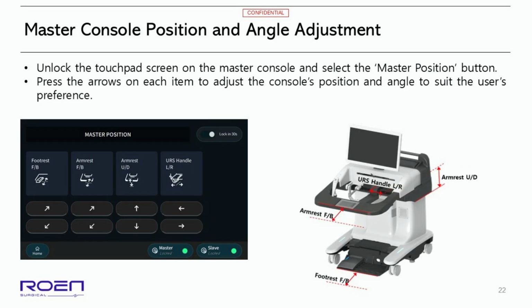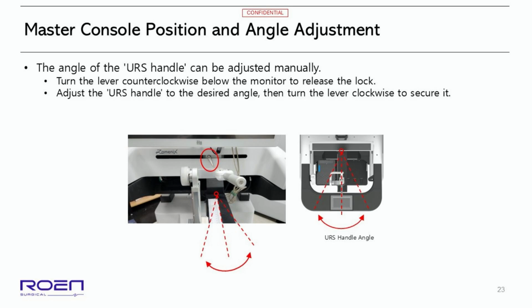Adjusting the position and angle of the master console. Unlock the touchpad screen on the master console and select the master position button. Press the arrows on each item to adjust the console's position and angle to suit the user's preference. The angle of the URS handle can be adjusted manually. Turn the lever counterclockwise below the monitor to release the lock. Adjust the URS handle to the desired angle, then turn the lever clockwise to secure it.